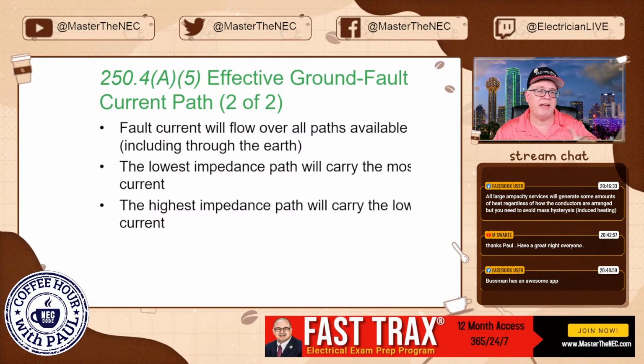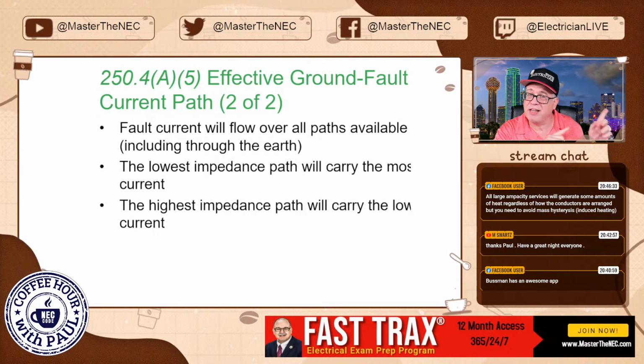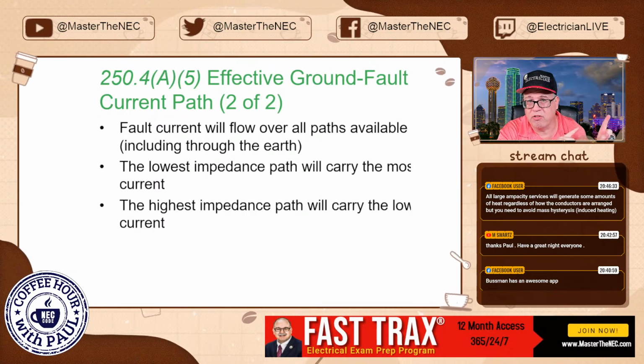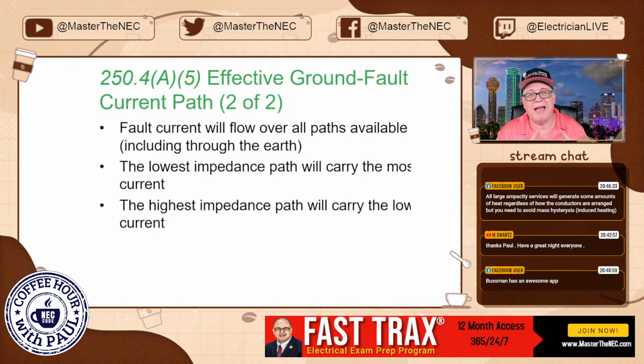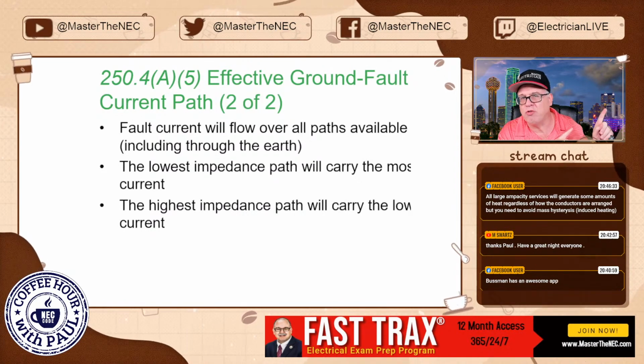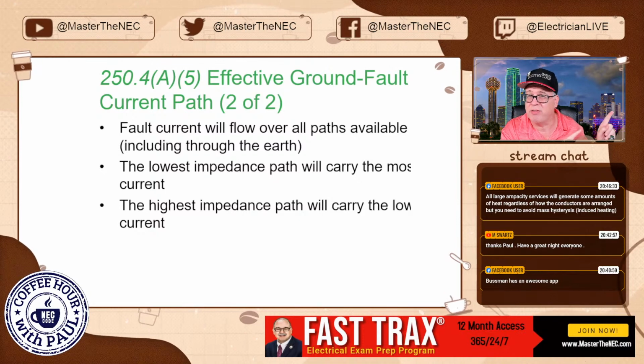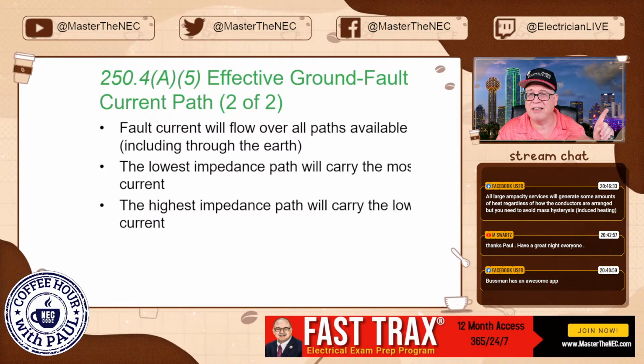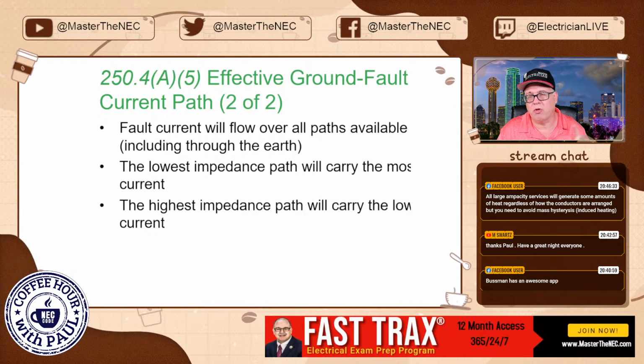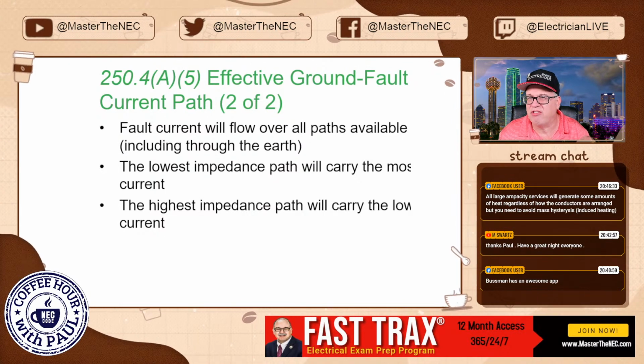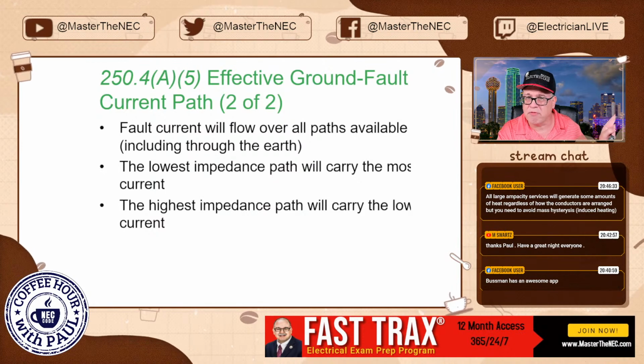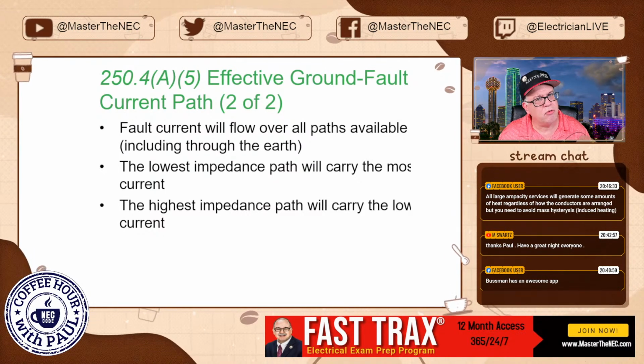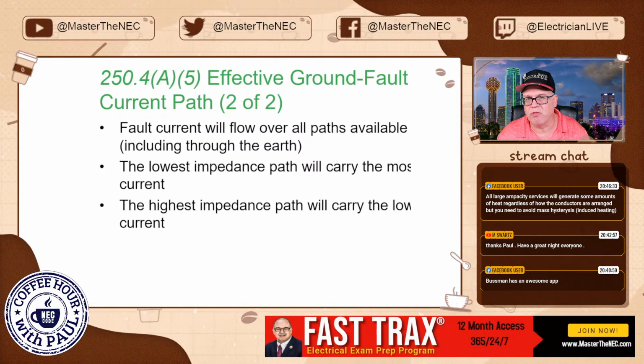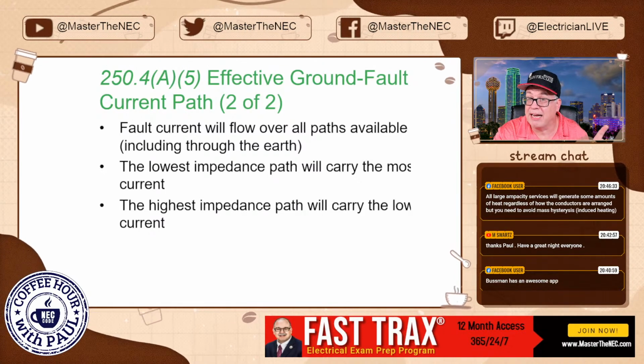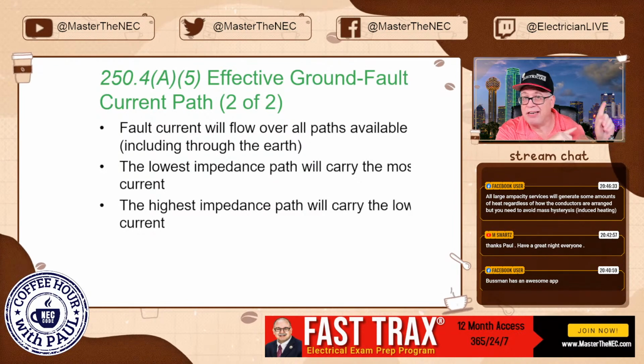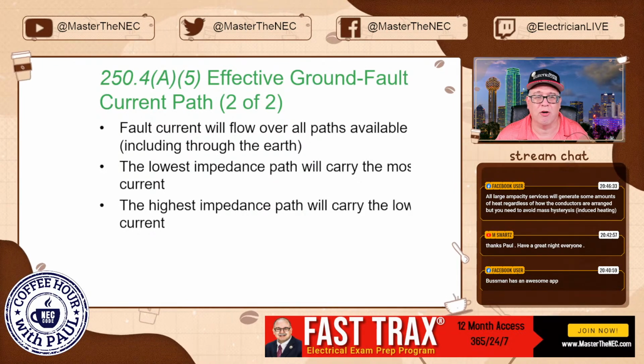Now, that doesn't work the same for utility folks. Because for the utility folks, they're dealing with a high level of voltage in low fuses, like 2 amp fuses, 3 amp fuses. They can use the earth for their application because they got a really high voltage. Do some Ohm's law and you'll see the difference, okay? So, sit down and do 7,200 volts and 25 ohms for ground rods, and then sit down and do 120 volts with 25 ohm ground rod, and you're going to see the difference. That's why they can do it and we can't, okay? We can't use the earth for that, okay?